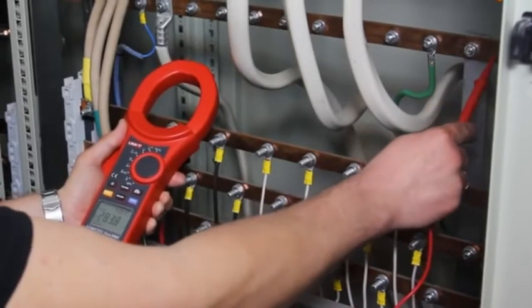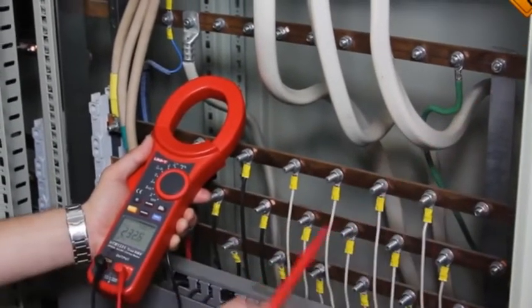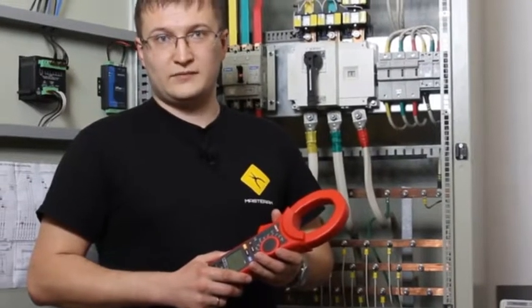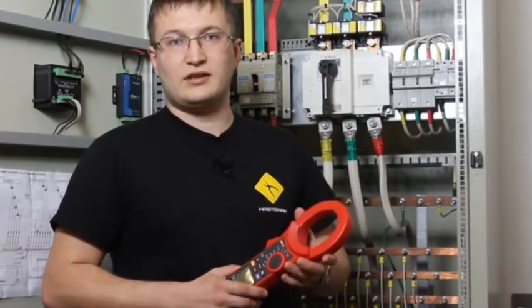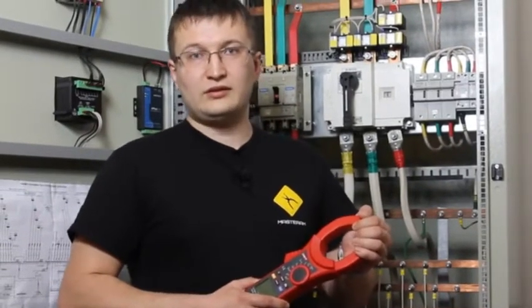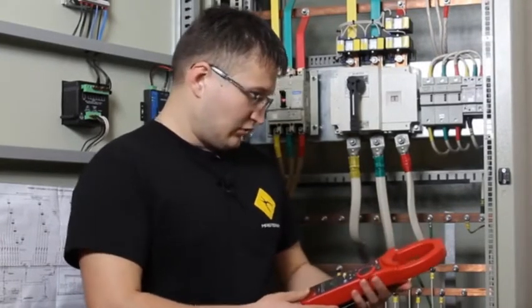The AC voltage is 232 volts. Now we want to demonstrate the possibilities of the analog output. It may help to better analyze the line current form, as most of the load is provided by electronics having switch mode power supply units. This means the current will be far from sine form. Let's check this.